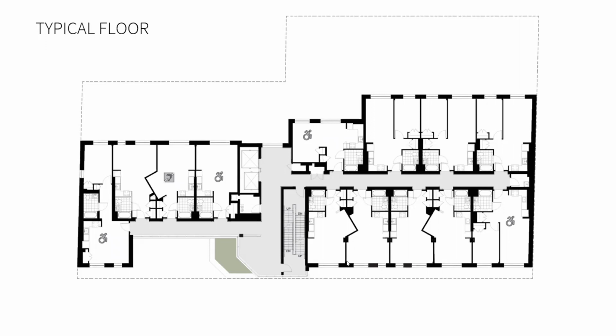And we also are using VRFs, and the risers for the VRF, the refrigerant, are on the exterior wall, which is very close to the evaporator. So it reduces the distance of horizontal runs of refrigerant, which increases the efficiency, reduces the embodied energy of the whole project, reduces potential for leaks. So that is another reason why most of our units are stacked vertically, and we don't change the layout as few times as we can.